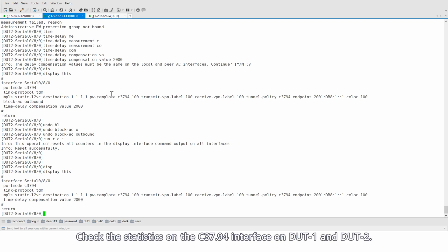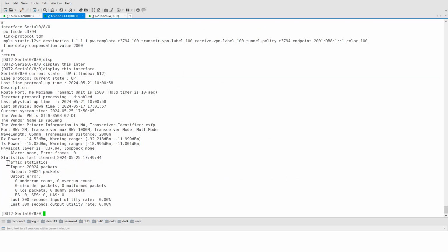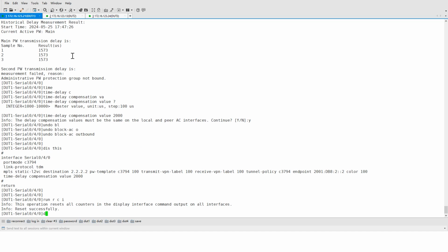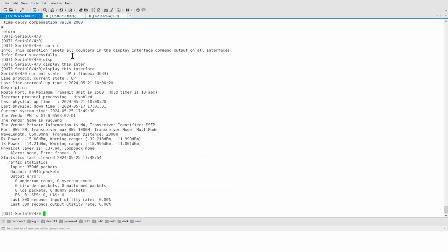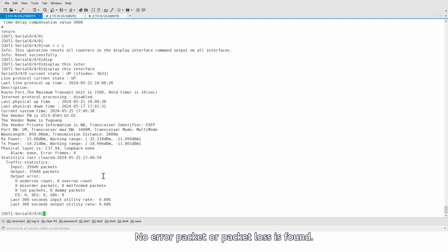Check the statistics on the C37.94 interface on DUT1 and DUT2. No error packets or packet loss is found.